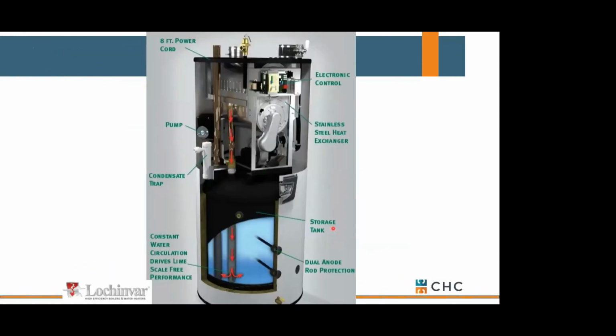When you open that up, you'll see that, oh, look at that. They've got a dedicated water heater inside the jacket. And below it, they've got a smaller storage tank and a circ pump. So they are simply circling water back and forth between a pretty good size heater and a smaller storage tank to develop some pretty nice capacities. So that's, I don't want to say a game, but a convenience in the fact that it looks like a tank type water heater with really good performance behind it.